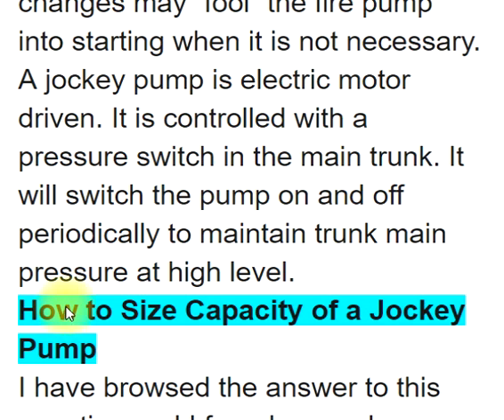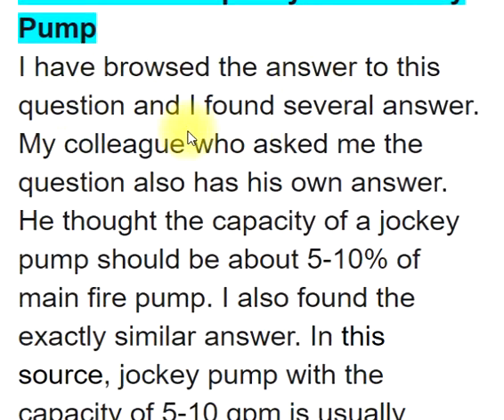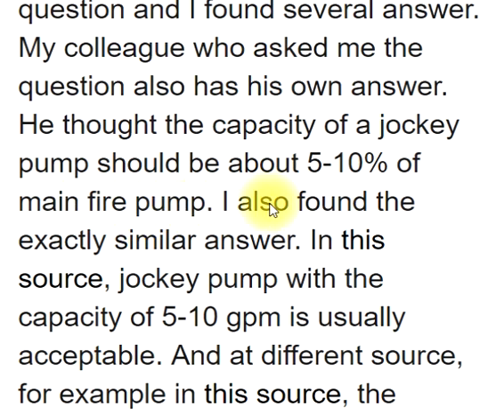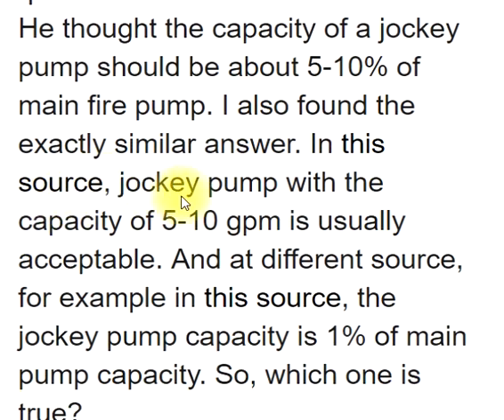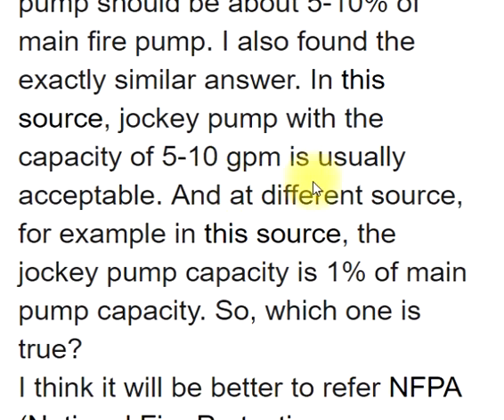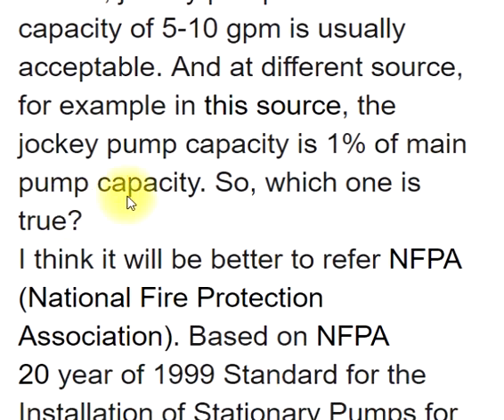How to size the capacity of a jockey pump? After researching this question, several answers were found. One common answer is that jockey pump capacity should be about 5–10% of the main fire pump. Another source states that a jockey pump with a capacity of 5–10 GPM is usually acceptable. A different source indicates the jockey pump capacity should be 1% of main pump capacity.